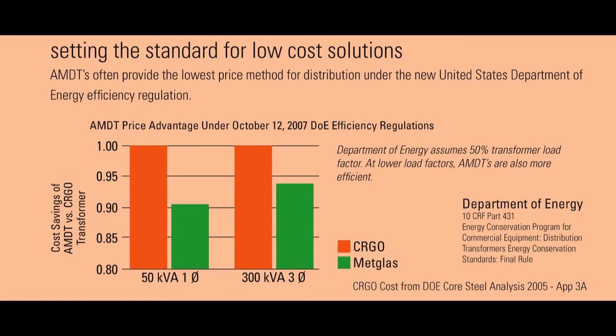So being thin lowers a second component of energy losses called eddy current losses. So we're amorphous and we're thin. If you have a distribution transformer sitting there, even with no load on it, it's burning energy—it's taking electricity from the grid. Those are called no-load losses, and they're 24 hours a day, 7 days a week, always like standby power.